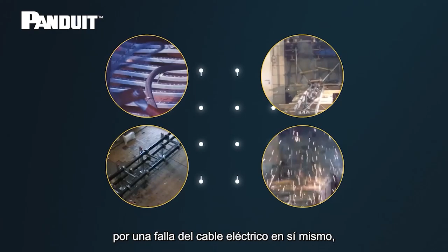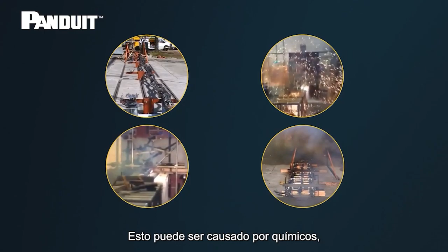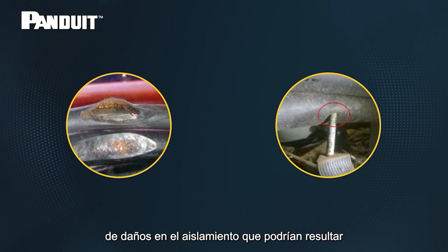So now I'd like to talk a little bit more about a short circuit event itself and the implications it has on the products in the market. Short circuit events are traditionally caused by a breakdown of the electrical cable's wire insulation, which could be caused by chemical, thermal, or even manufacturing defects. But at the end of the day, the vast majority of insulation jacket failures happen because of mechanical causes—damage during packaging, shipping, or deployment of the cable into a facility. Regardless of the cause, anytime the insulation is damaged, you open yourself up for a short circuit event. I've given a few images here to help highlight some real world examples of insulation damage that could result in a short circuit event.